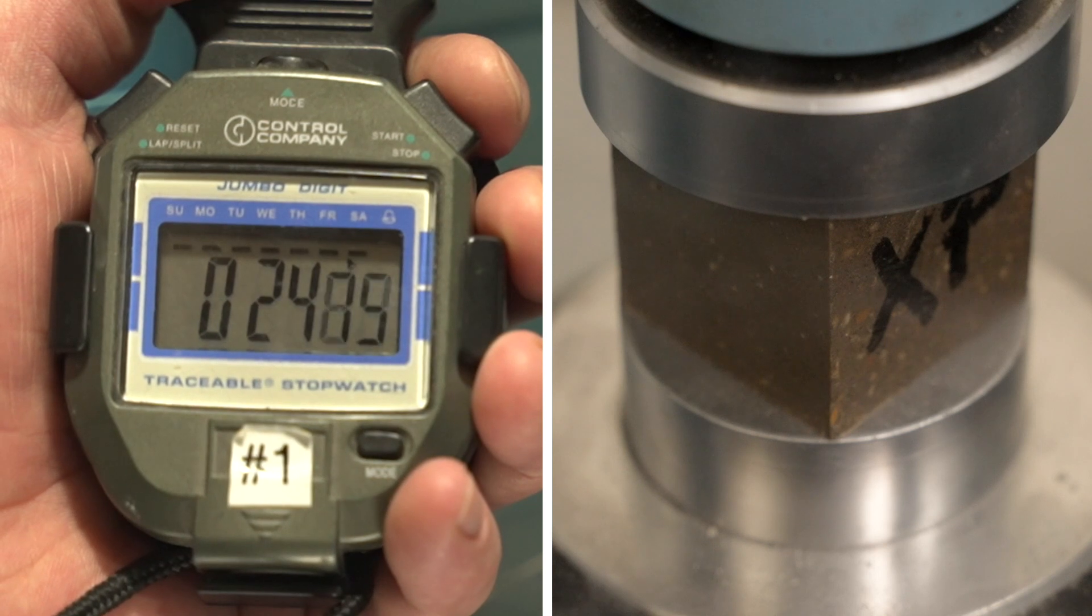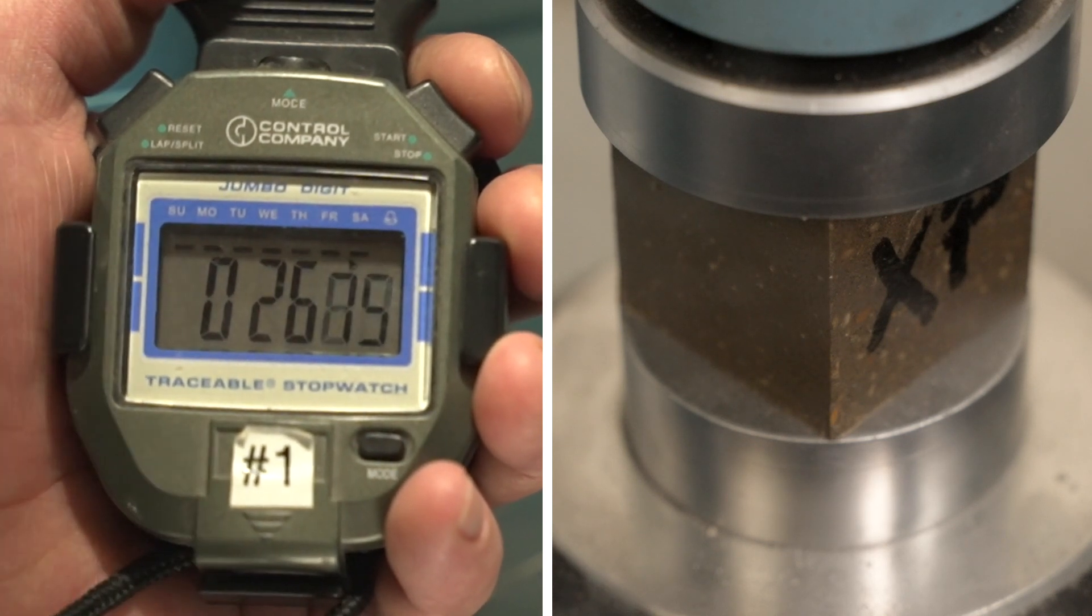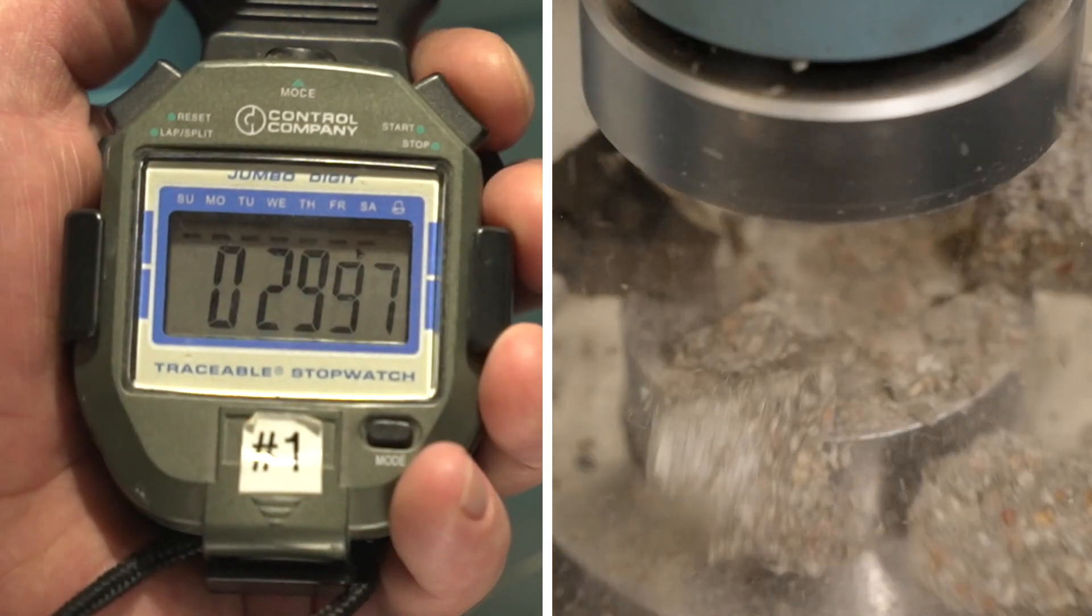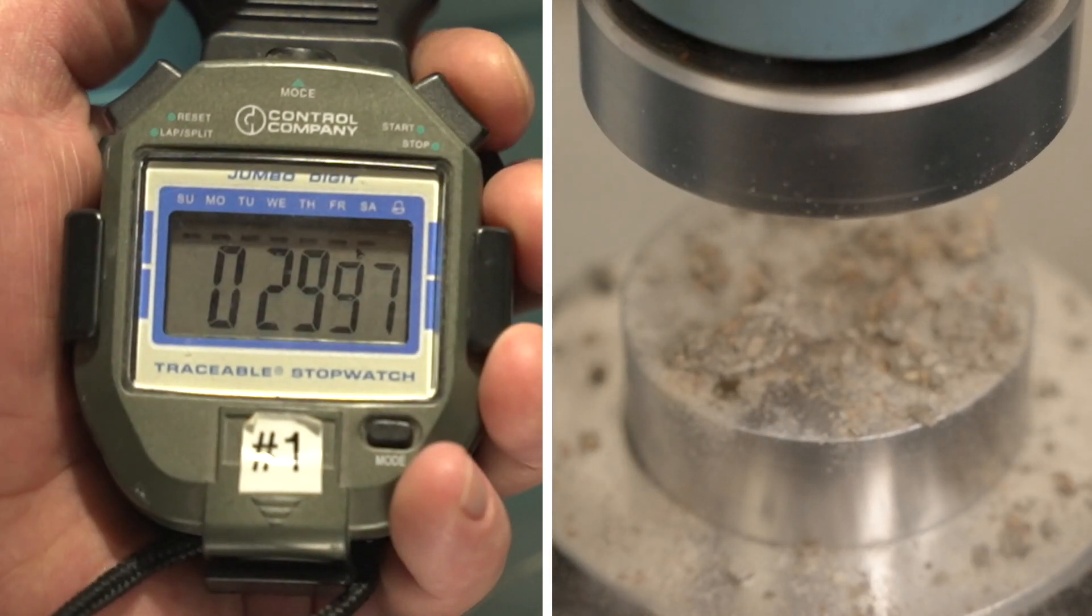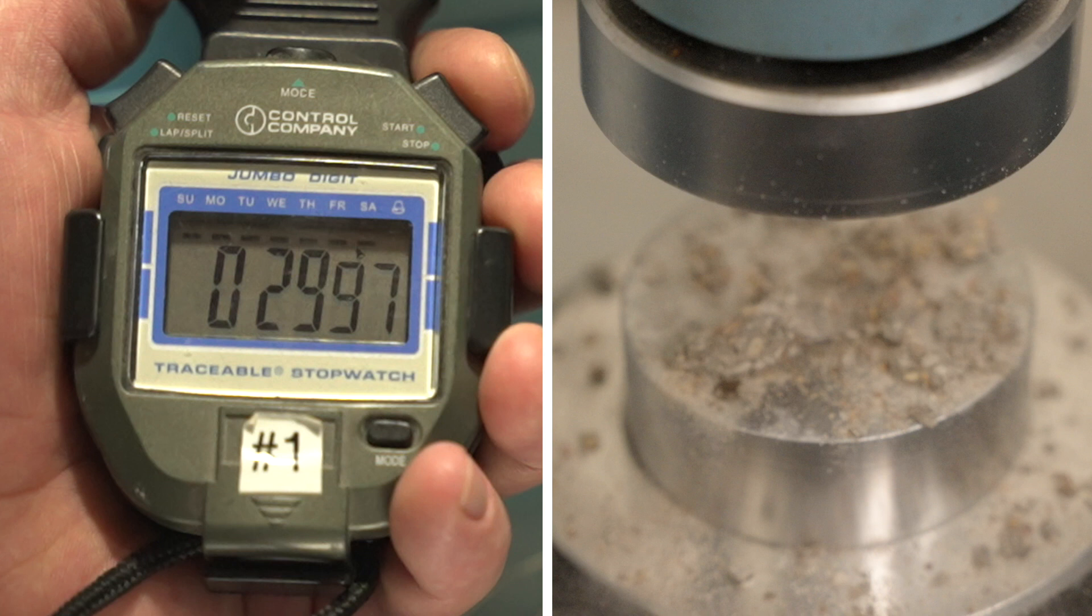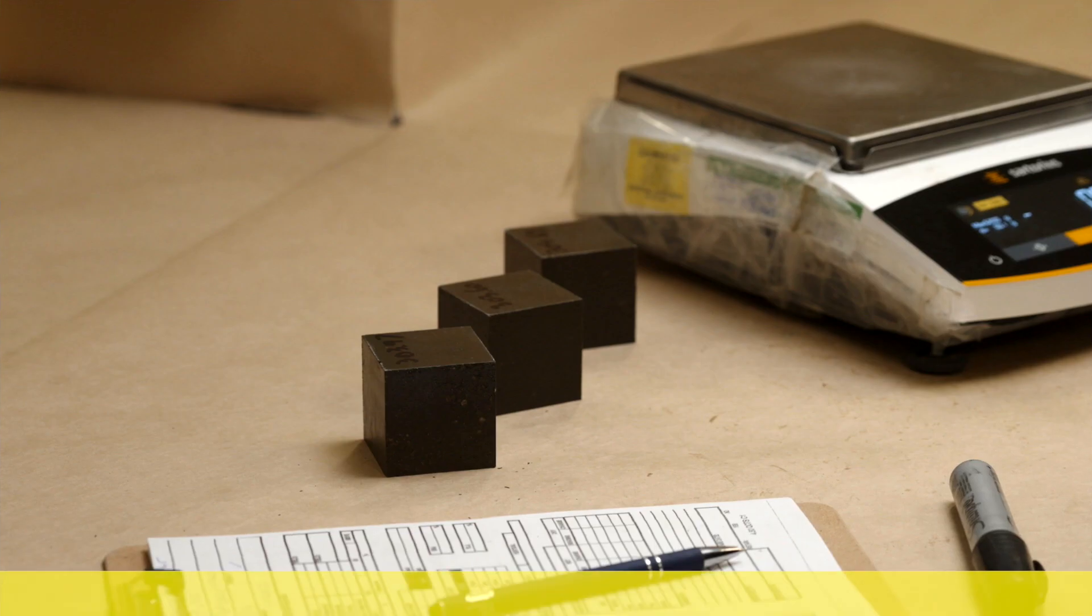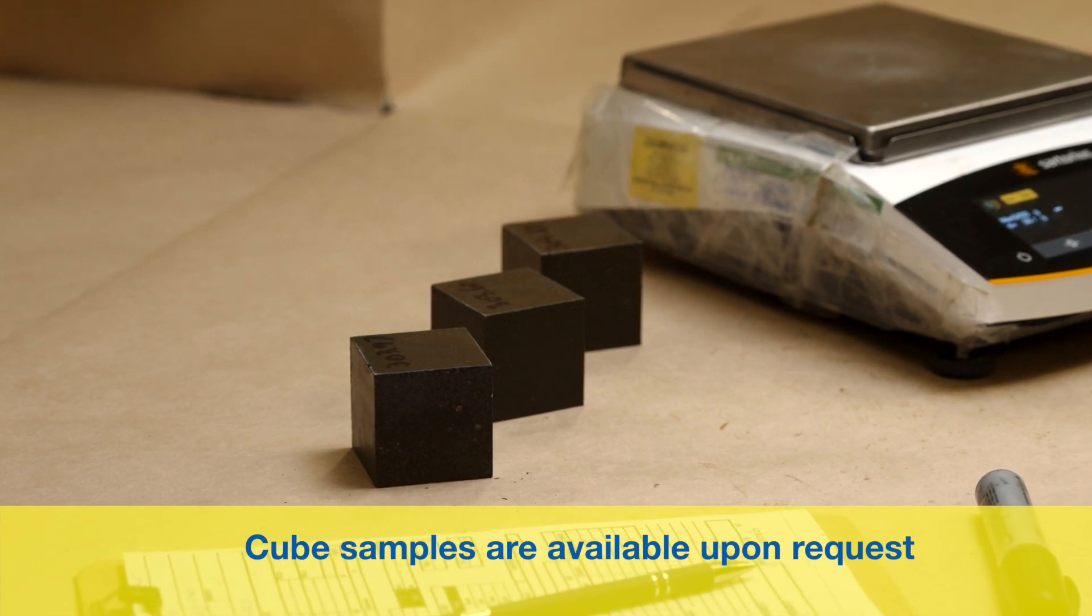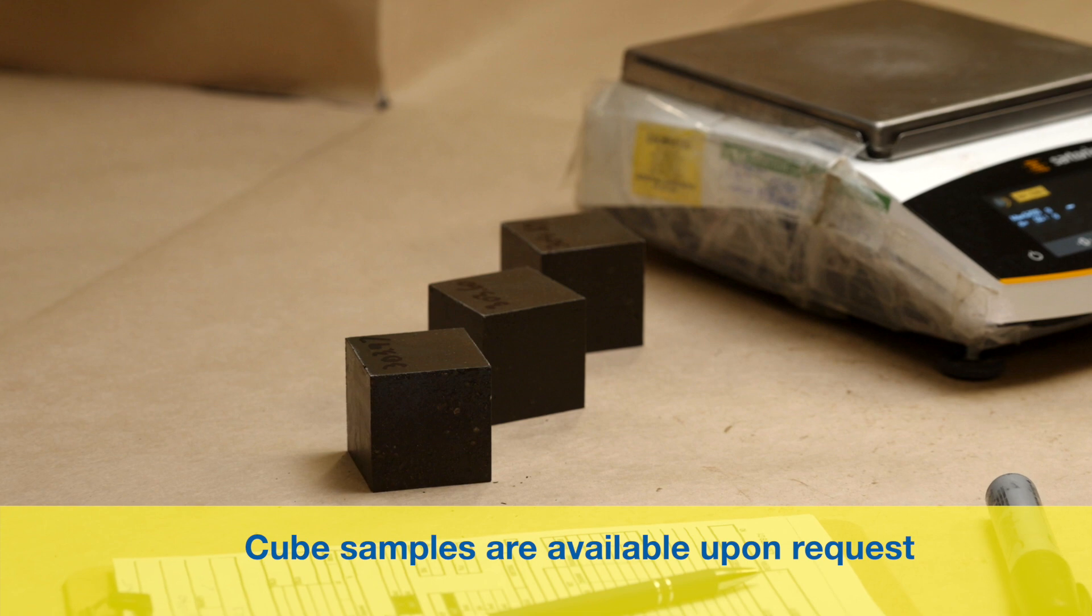By doing so, you can be sure that the test machine is running at load rate 2, even when loaded. Machines that run at position rates substantially slower than the prescribed 0.25 inches per minute while loaded will yield artificially low compressive strengths. 5-star products will make samples of prepared epoxy grout cubes available upon request to be used for machine calibration.